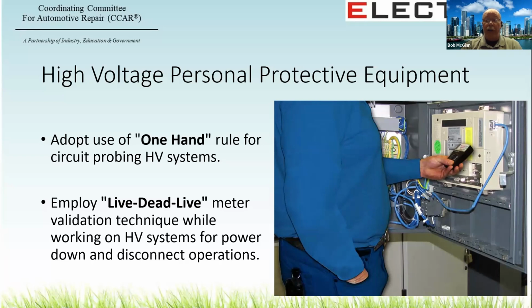reference power source. This is particularly helpful when we are checking for power down on a hybrid or electric to make sure that zero is actually zero. To test the meter function before checking the system, zero volts, which we would require in disconnect verification, check the meter on a battery or a reference test voltage, then test the high voltage circuit for 0 volts, then immediately back to your reference. Your live is the battery or your reference, your zero or your dead is the high voltage vehicle to make sure that zero is actually zero, and then back to the reference point to prove the meter function is correct, live dead live.